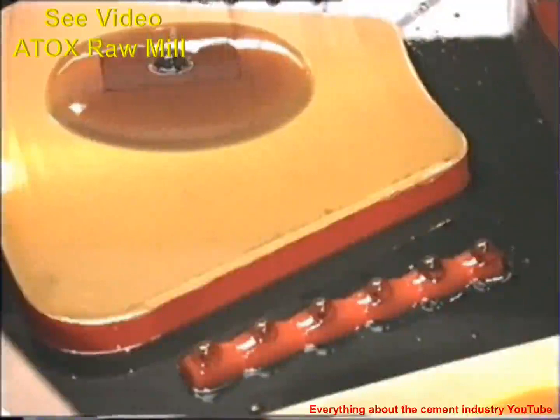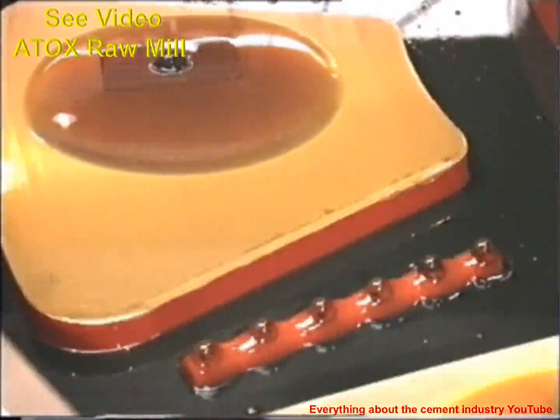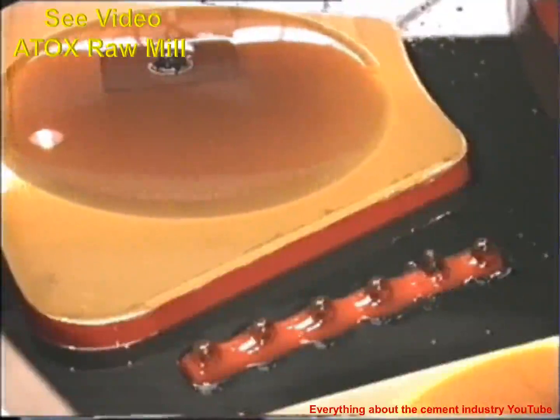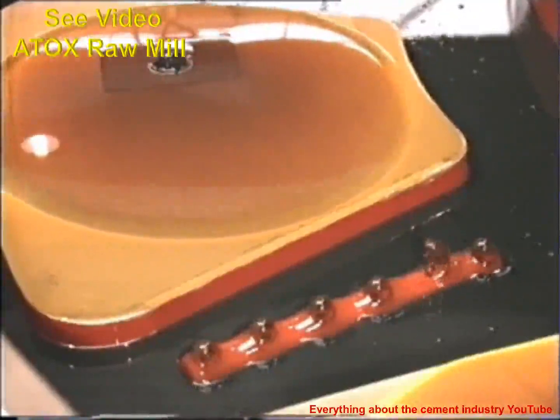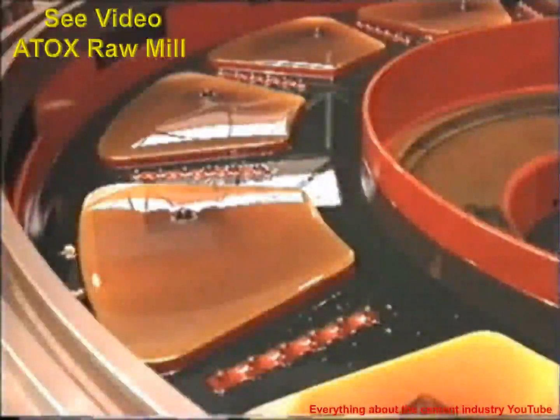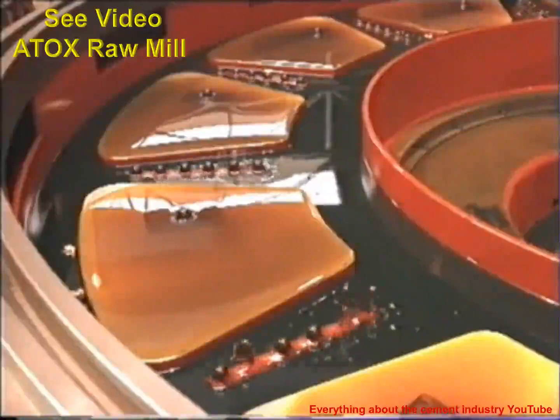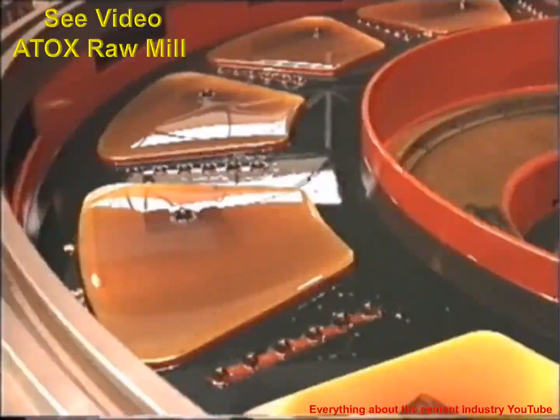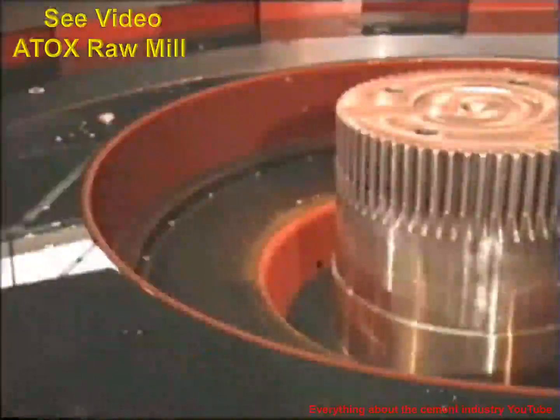Cooled, low-pressure oil is supplied at the oil inlet zones between the thrust pads. Each bearing shoe is also provided with a pressure pocket, through which high-pressure oil is supplied, giving the thrust bearing its hydrostatic effect. Both the low and high-pressure lubrication systems are filtered with 10-micron filter elements, integrated with the oil supply unit.